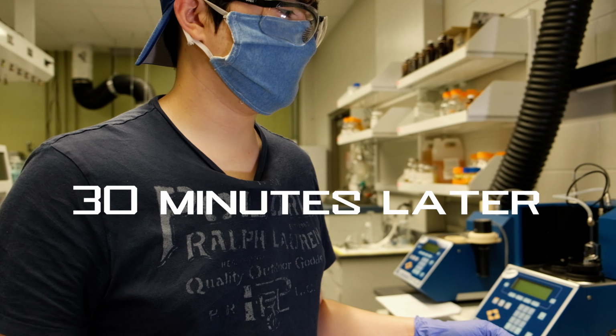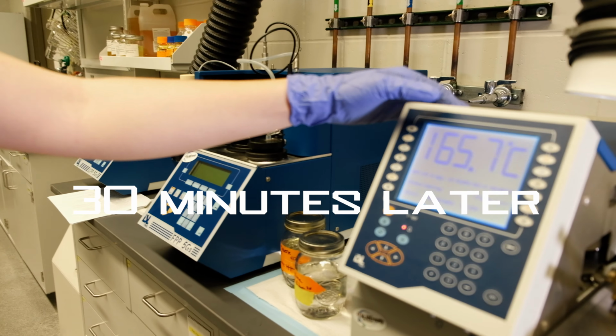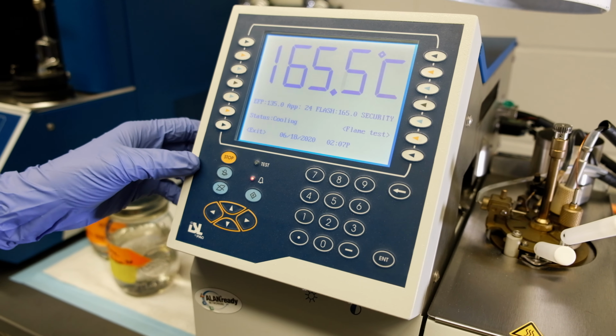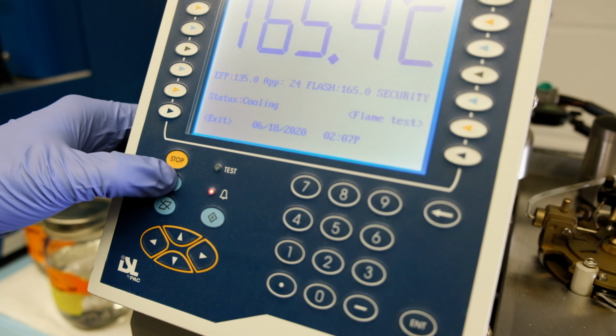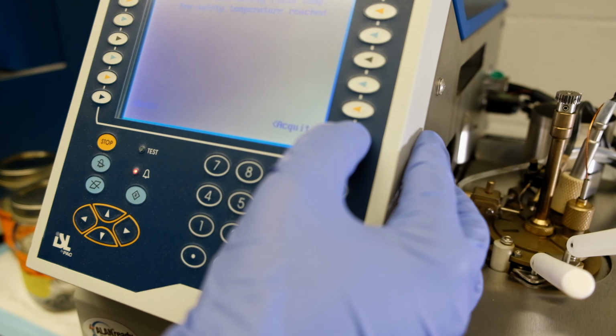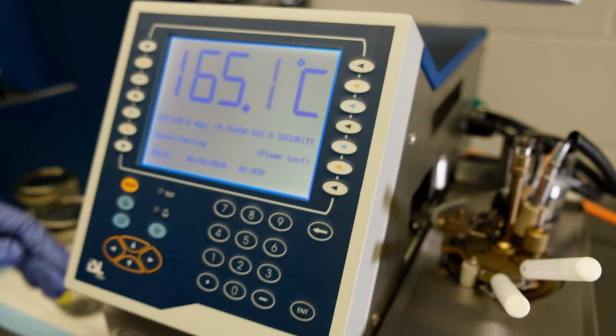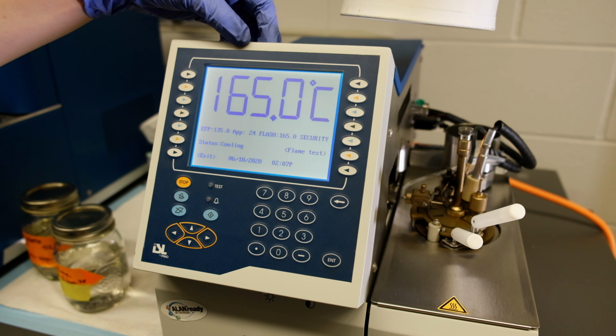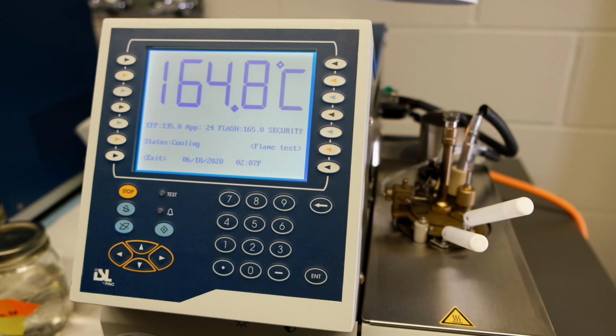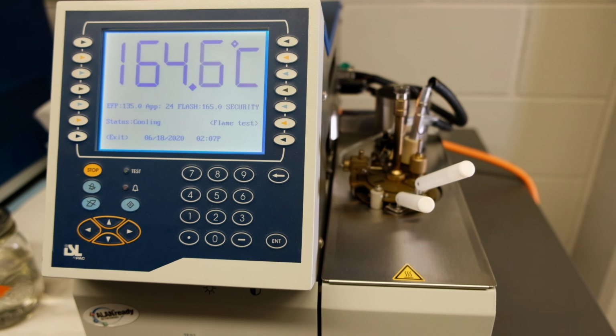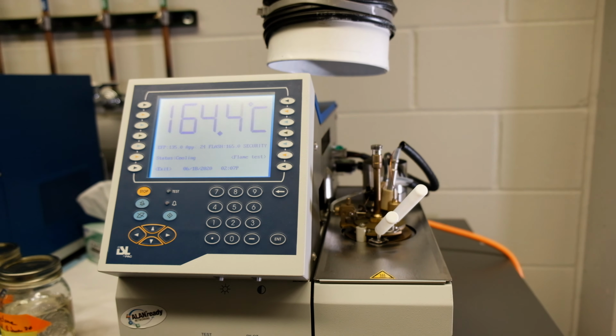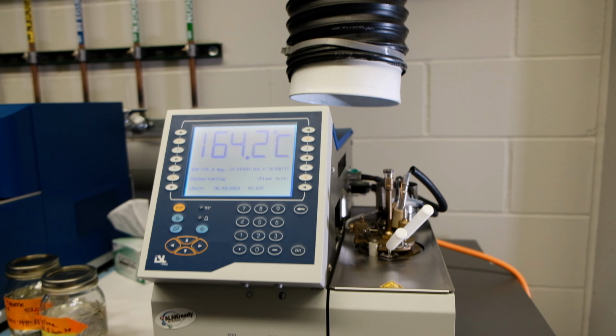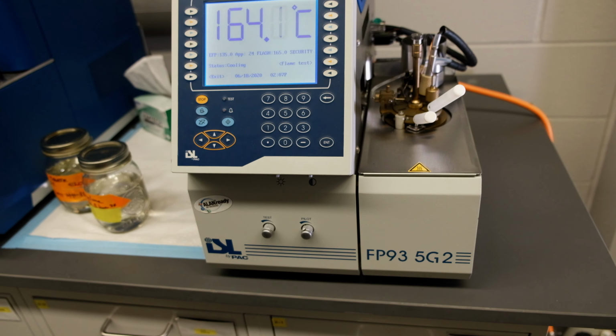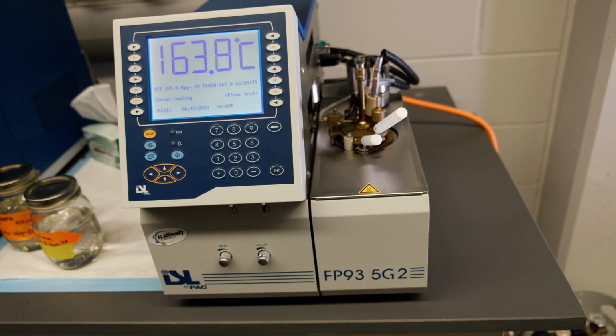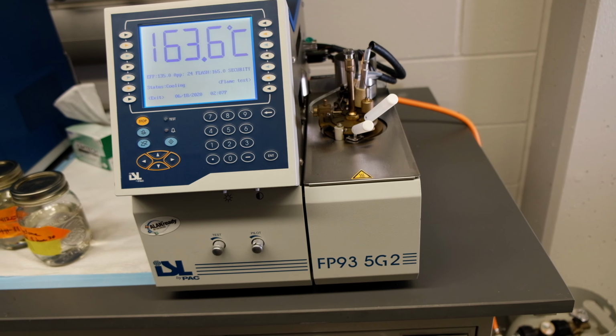So when the test is finished, you'll come across this alarm here. To get rid of it, you just go over here to this alarm button, hit that in the bottom right here, go quit, and that should shut it off. And it'll start the cooling process, and this will just start dropping the jacket temperature. Don't start taking stuff apart and cleaning stuff until it reaches at least 55 degrees Celsius. At that point, you are free to start the cleaning process and take things apart and start disposing of the biodiesel.